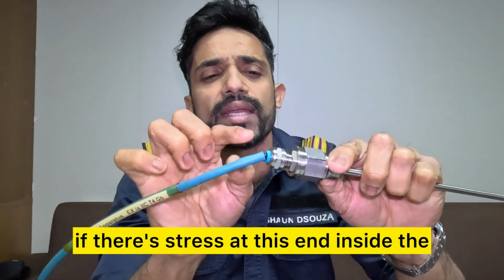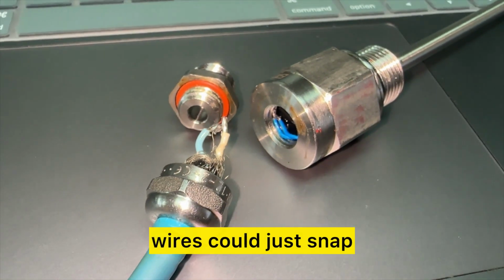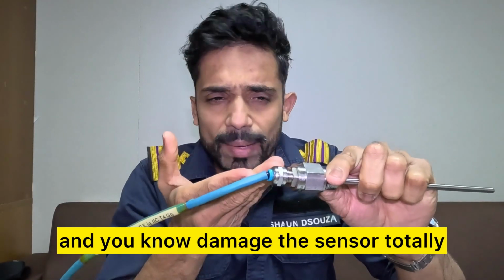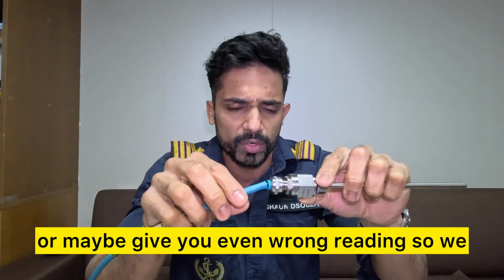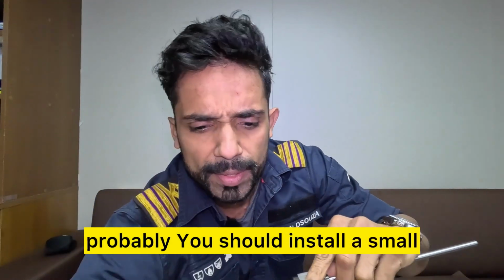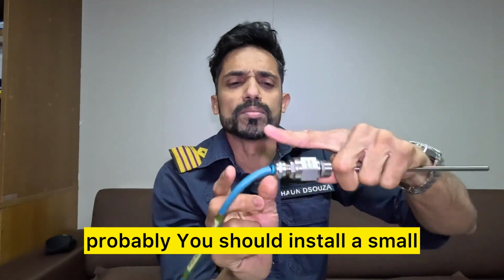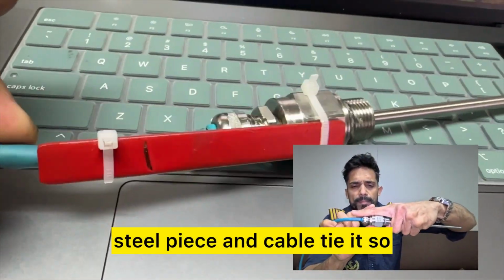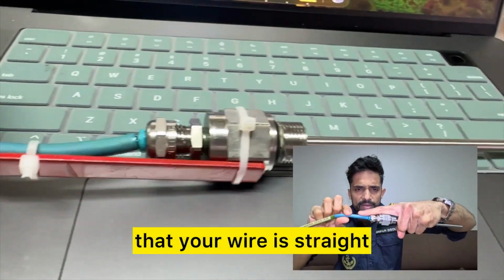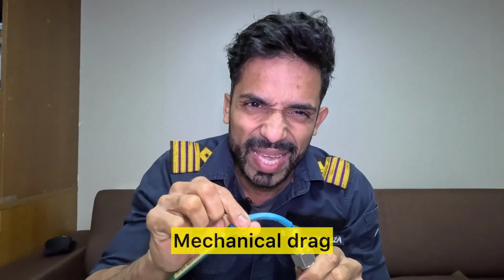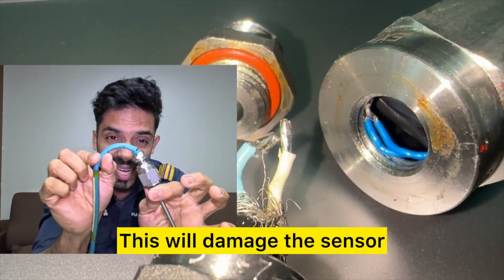If there's stress at this end, the wires inside could snap and damage the sensor totally, or give you wrong readings. You should probably install a small steel piece and cable tie it so your wire is straight. Remember this term, mechanical drag — it will damage the sensor.